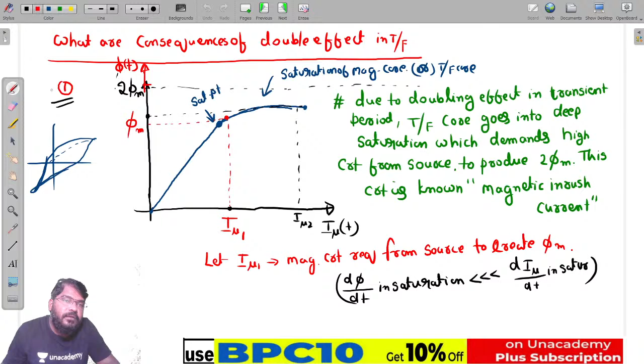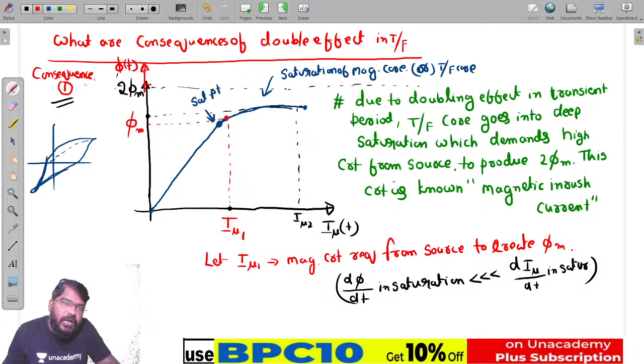Next, this is consequence 1. The transformer goes into deep saturation, which demands a high magnetizing current from the source, in order to produce 2 times the maximum flux. That current is known as the magnetizing inrush current.